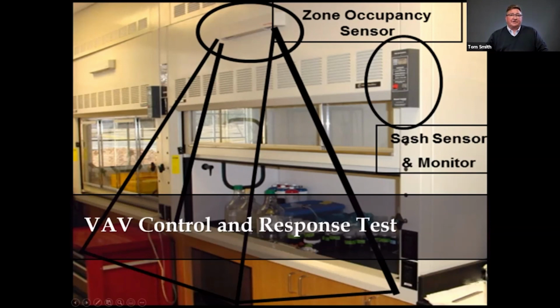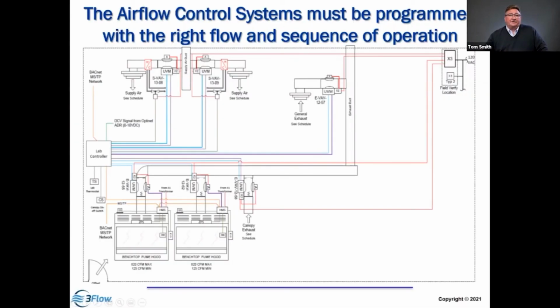A hood can be modulated based on sash sensors that measure the position of the sash. They can be modulated by zone presence sensors. They can be modulated by airflow velocity sensors. So looking at these different mechanisms of control, when we first look at a laboratory, a newly installed hood, we'll say, what's the sequence of operation for the controls? What do we expect to occur?